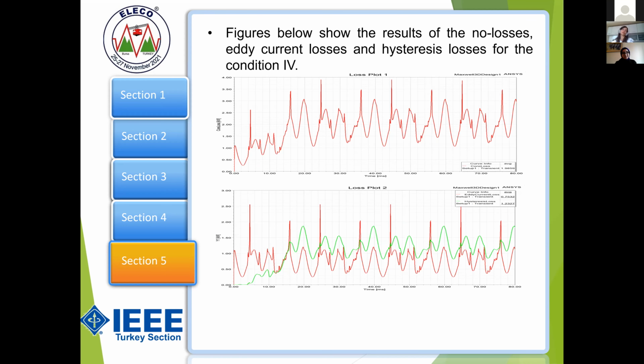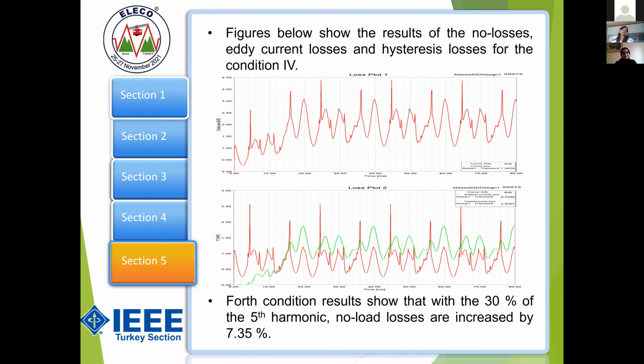Similarly, in the fourth condition, we increased the fifth harmonic by 30%. In the previous case, the no-load loss was just 1.88 kilowatt with the same percentage of harmonic, but when we replaced the third harmonic with the fifth one, it increased to a higher level. So the effect of the third harmonic and the fifth harmonic is not the same. The results show that.